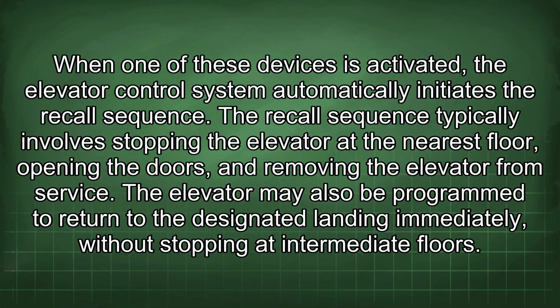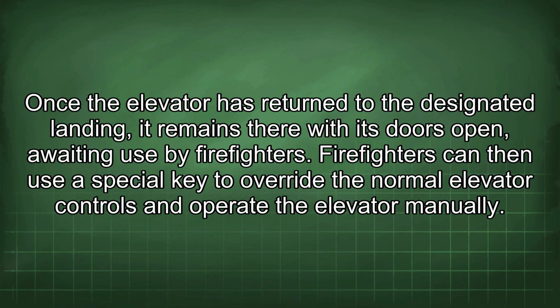When one of these devices is activated, the elevator control system automatically initiates the recall sequence. The recall sequence typically involves stopping the elevator at the nearest floor, opening the doors, and removing the elevator from service. The elevator may also be programmed to return to the designated landing immediately, without stopping at intermediate floors. Once the elevator has returned to the designated landing, it remains there with its doors open, awaiting use by firefighters. Firefighters can then use a special key to override the normal elevator controls and operate the elevator manually.